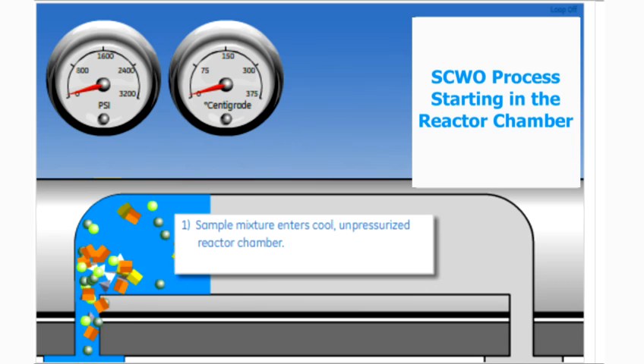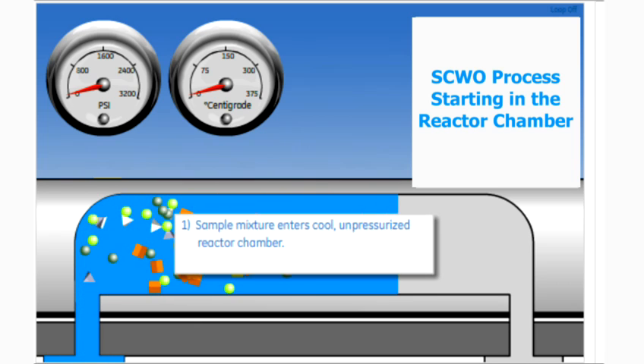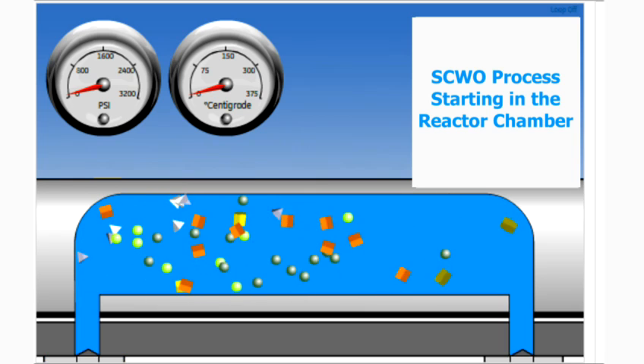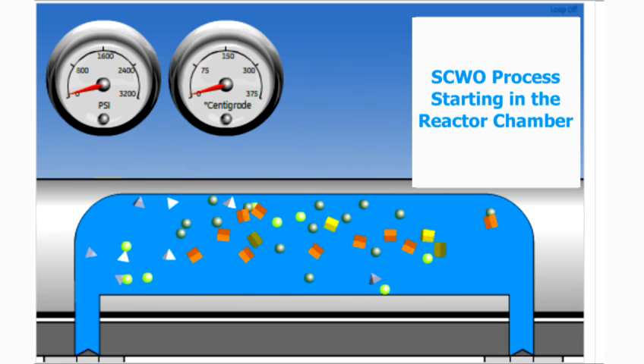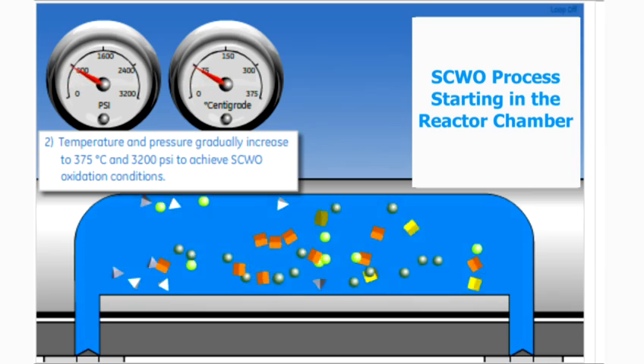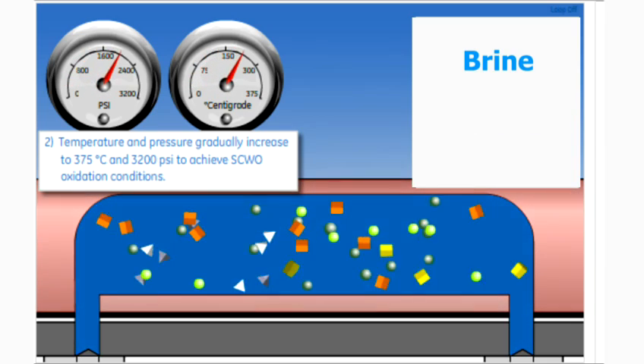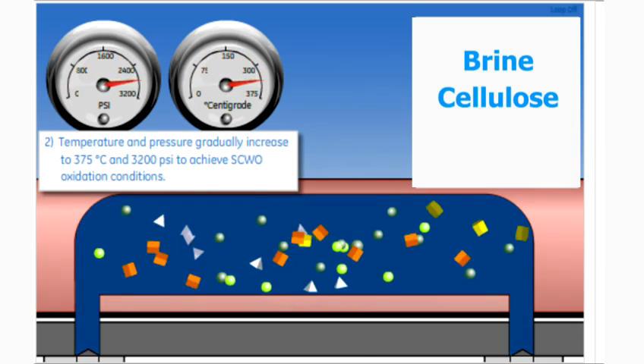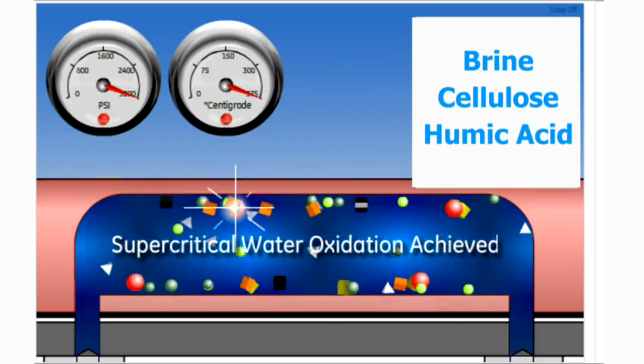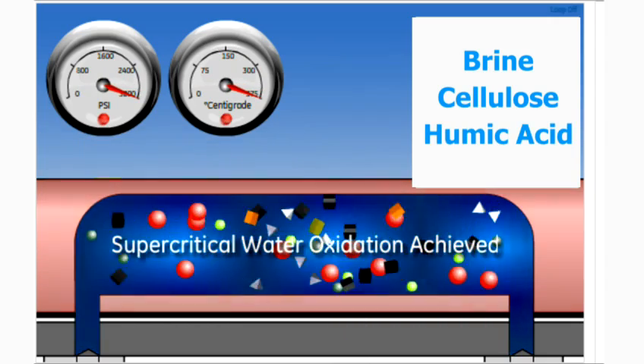The Innovox is robust. The SCWO technology uses elevated temperature and pressure to oxidize samples efficiently. You can run thousands of tough samples – including brine, cellulose, or humic acid – by simply replenishing your reagents as needed.